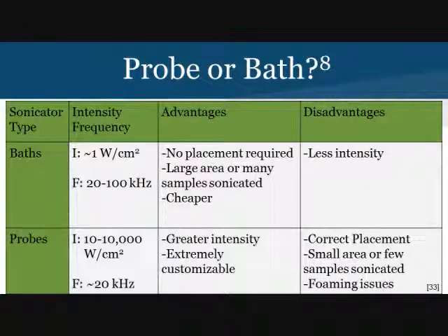Here is a slide showing the advantages and disadvantages of using a probe or a bath. Usually, probes are favored because of their wide intensity range, but often have issues with foaming and the need to be precisely placed in your sample to obtain the best results. Baths are cheaper and can run multiple samples simultaneously, but often are not nearly as intense as probes.